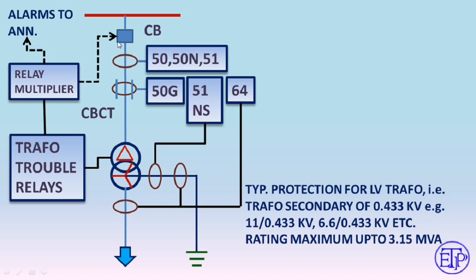There are also transformer trouble relays physically connected with the transformer. Inside the switchgear panel there is a relay multiplier — electromagnetic relays that multiply the contacts — from which trip signals are sent to the circuit breaker and alarm signals to the annunciator. We will now check what the transformer trouble relays are.